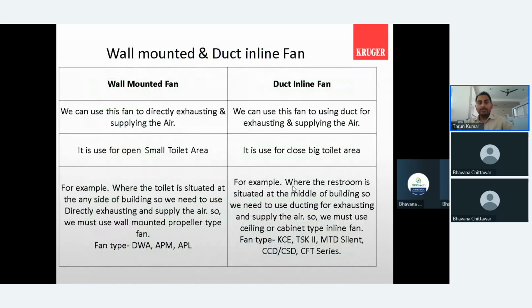So basically, for the wall mounted fan and duct inline fan, we can use a wall mounted fan directly for exhaust and supply, fixed into the wall. A propeller fan can be used for a small or open toilet area, wherever in a building you don't have much space to put the fan. There we should always go with the propeller fan. And the inline fan is for when you have a huge, bigger room and your air volume is huge, so then you can go with the inline fan.